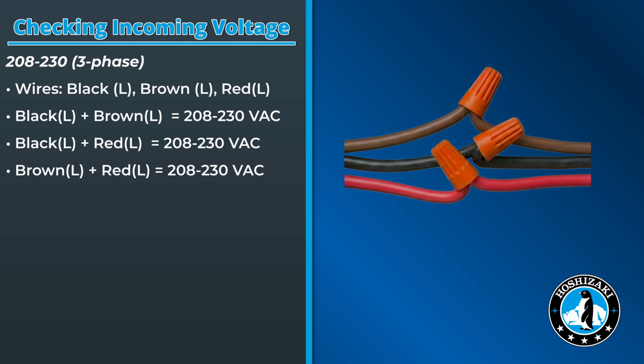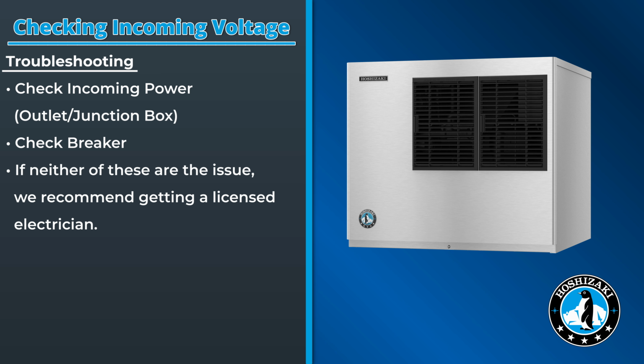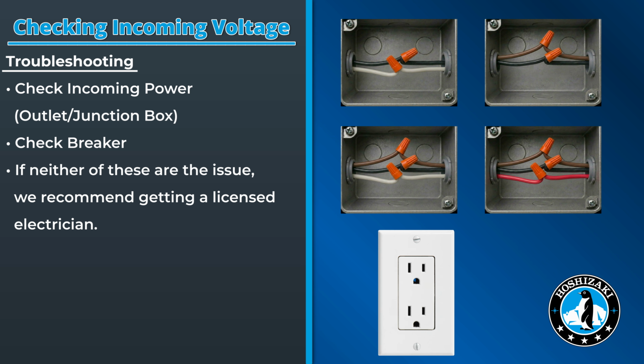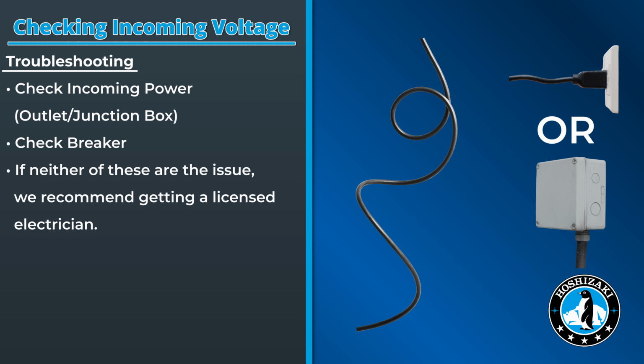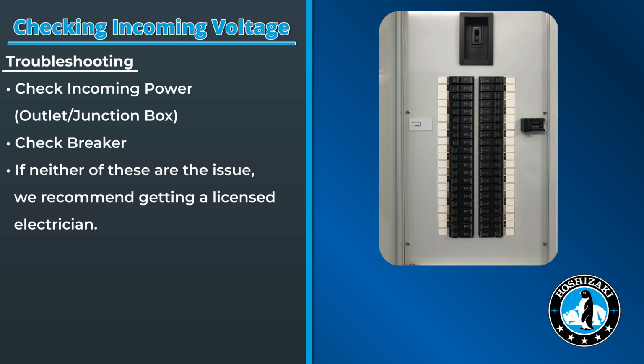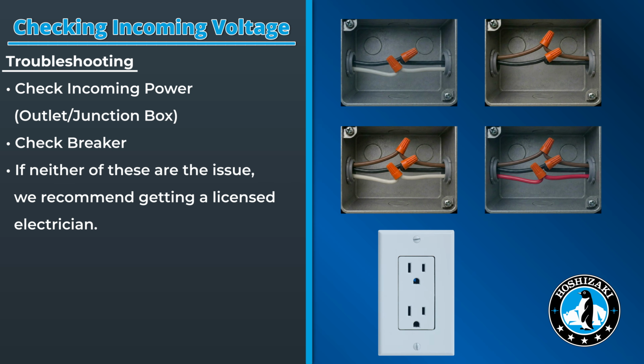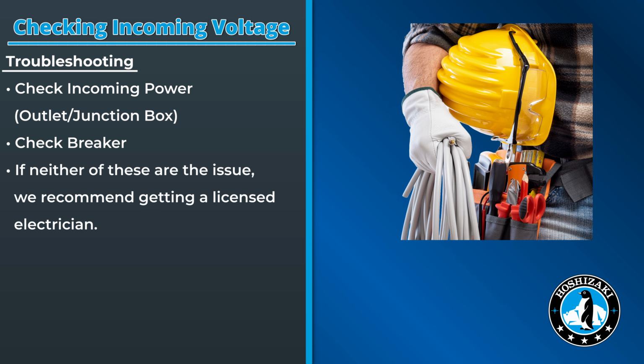For 208/230 volt three-phase units, there will be 3 line wires or 3 hot wires: black, brown, and red. When checking voltage between any 2 of these wires, the reading should be between 208 and 230 volts. If you're getting incorrect voltage readings at the machine, the next step is to check the voltage directly at the outlet or junction box. If the voltage at the junction box is correct, the issue is likely within the power cable going to the unit. If there is no power present, verify that the breaker is not tripped. Once you confirm that the breaker is not tripped and you verify there's no power at the junction or incorrect power at the junction, please contact an electrician.